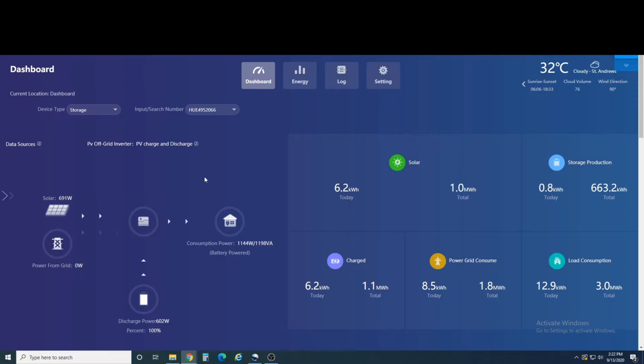The other set point that you can set in there is your low voltage disconnect, and that's basically you set whatever safety point that you want for your batteries. In the case of this, I have mine set at around the equivalent of about 10% of the battery remaining. And so when you hit that point, it'll shut itself off, and then my battery management system, the BMS on the batteries, it's actually set to cut them off when they hit around 5 or 6%.